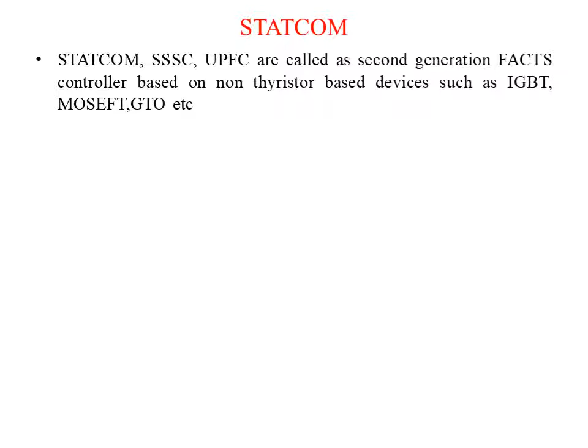So STATCOM, SSSC, that is static synchronous series compensator, and UPFC are called second generation FACTS controllers based on non-thyristor type devices such as IGBTs, MOSFETs, GTOs. So instead of thyristors, they are using IGBTs, MOSFETs, and GTOs, transistors. STATCOM is a shunt connected reactive power compensation device which can generate or absorb reactive power and in which the output can be varied to control specific parameters of an electric power system to which it is connected. So this STATCOM can be voltage controlled, that is VSI, or current controlled, that is CSI.